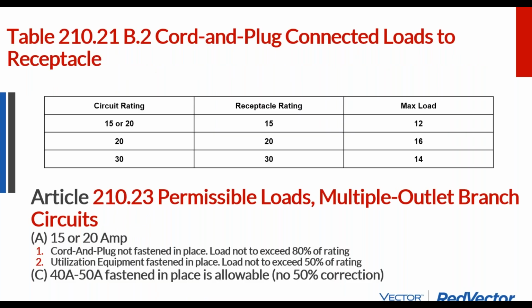and that's the rating of the circuit. That means you'll have all these 20 amp breakers, and they should only have 15 amp loads on them, 16 amp loads on them. So on a microinverter circuit, if it's limited to a 20 amp branch circuit and each microinverter is 16 amps each, you go up to 16 amps, and then you add on your additional 25% overcurrent allowance, and then you put it on a 20 amp branch circuit.